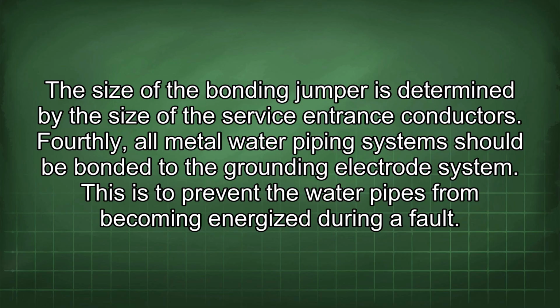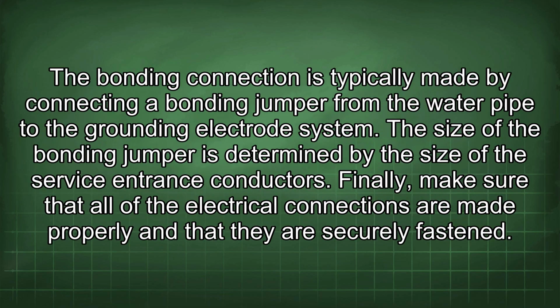Fourthly, all metal water piping systems should be bonded to the grounding electrode system. This is to prevent the water pipes from becoming energized during a fault. The bonding connection is typically made by connecting a bonding jumper from the water pipe to the grounding electrode system. The size of the bonding jumper is determined by the size of the service entrance conductors.